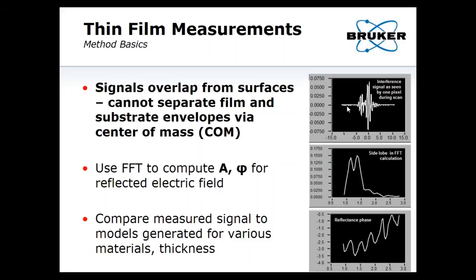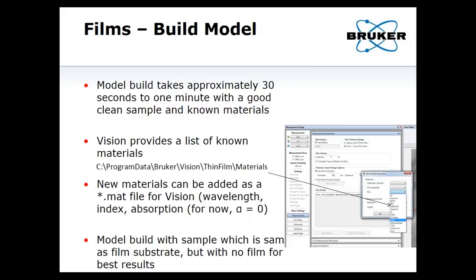How does this fitting actually work? Your reflection from the substrate and the film will interfere, so you see two overlapping envelopes giving a more complex modulation pattern. In the frequency domain, if you do an FFT, you can compute the amplitude and phase of the reflected field and get lobes in the frequency domain. You compare this to the expected results based on the system response measured with your reference sample. You get a merit function that gives you possible thickness results. Building the model takes about 30 seconds depending on your sample and measurement setup.